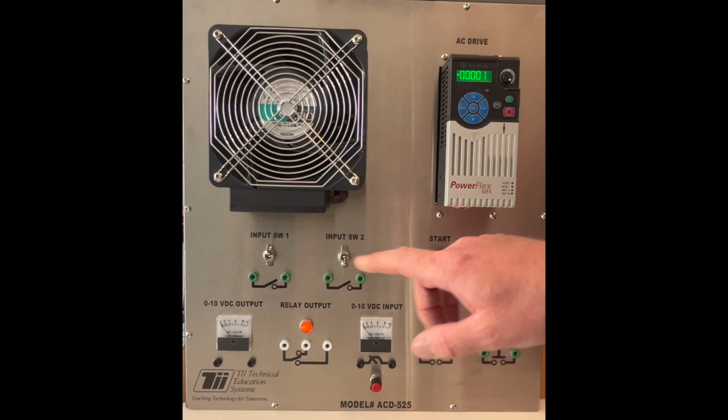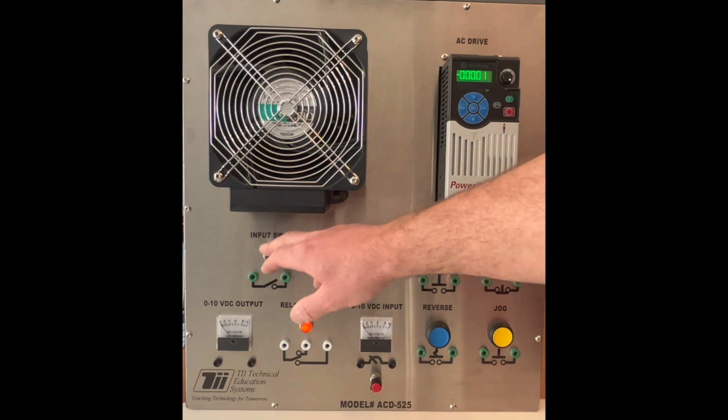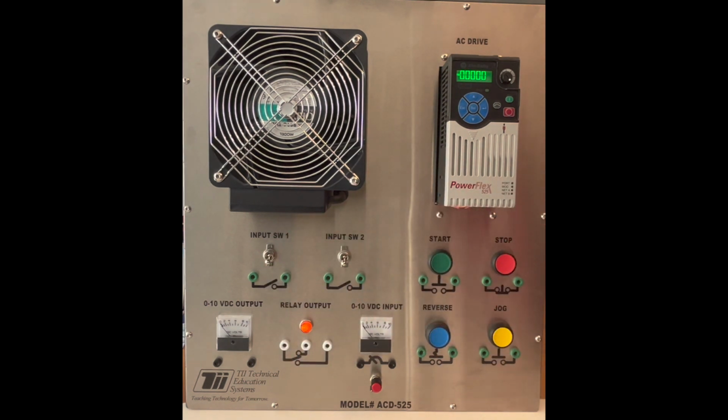So if sometime you're troubleshooting a VFD that's not ramping up to the right frequency, that could be a situation where you have a signal coming into one of the bits in your digital input status, and then you can go through and disconnect that. Let's say a wire popped off and is touching a positive and sending a signal to it, or if the switch has accidentally been activated.